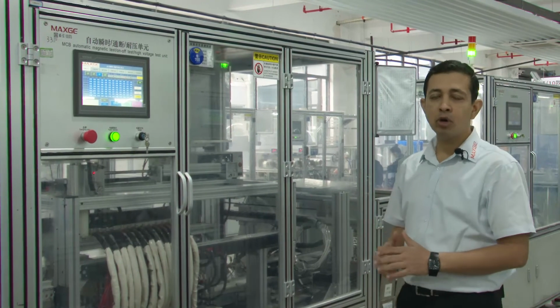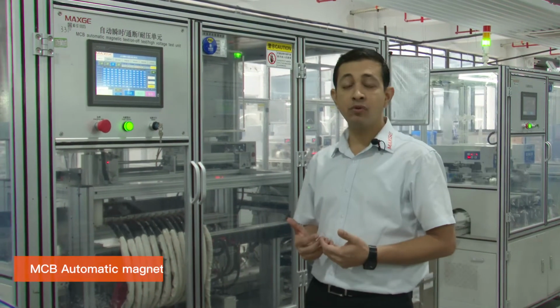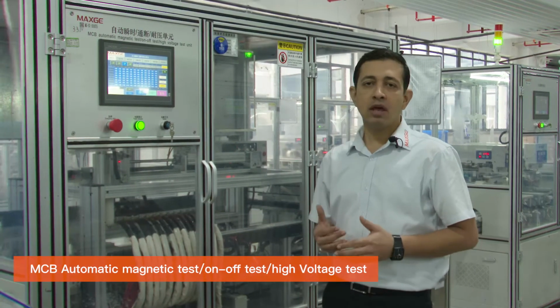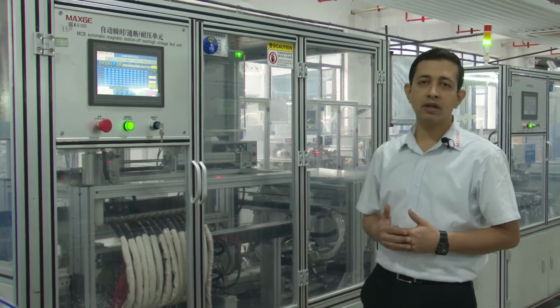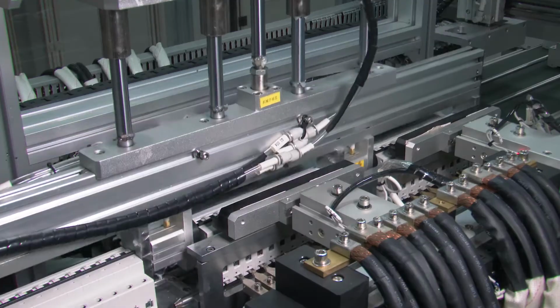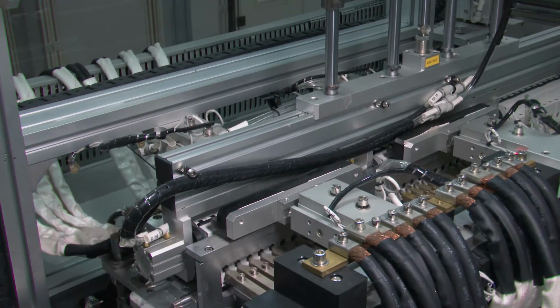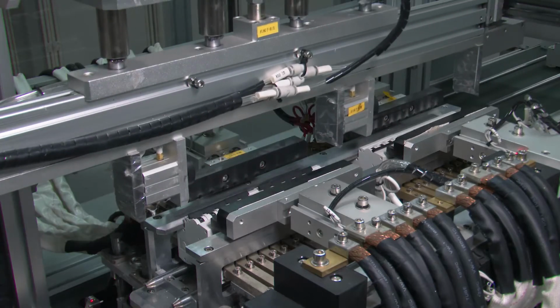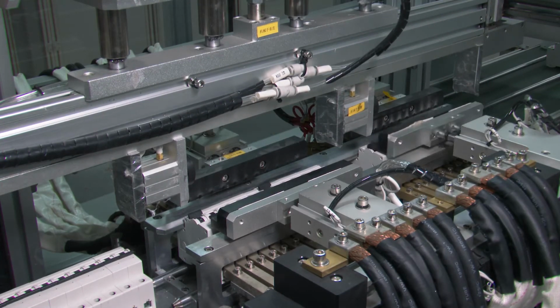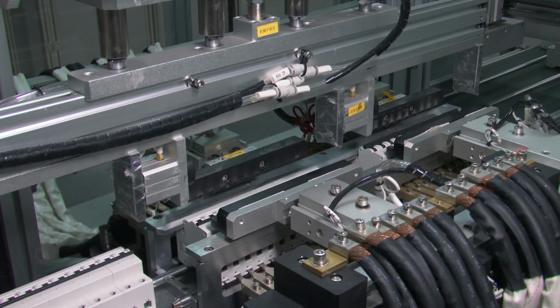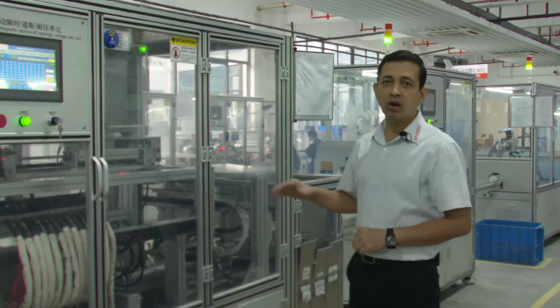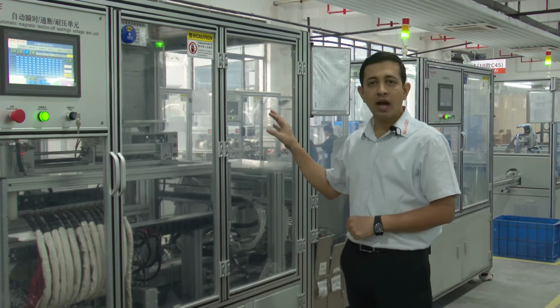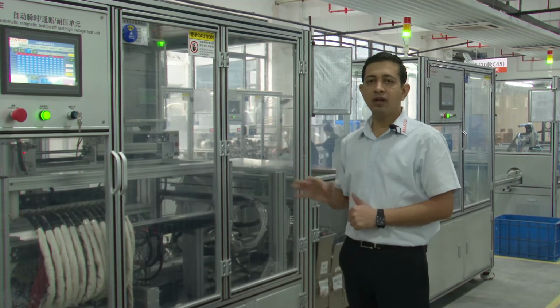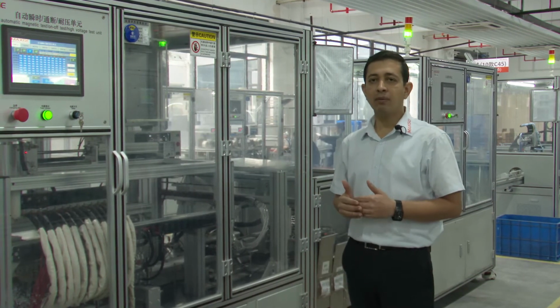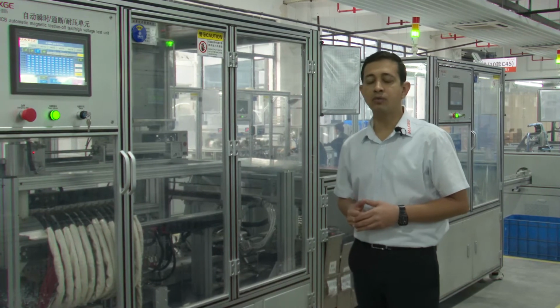Now we are standing at the multipole magnetic testing machine, because as we have done the multipole, we have to retest it for magnetic testing. Some of our competitors may not be checking the multipole again. As we have seen, this line also has the magnetic testing machine for the single pole, but after the multipole we have to recheck it again, because it has different characteristics after we couple all the poles together. This machine does automatic magnetic testing on the multipole, and it also does high voltage testing at 2.1 kV. We apply high voltage for 1 second, and the leakage current should not exceed 20 milliamperes.